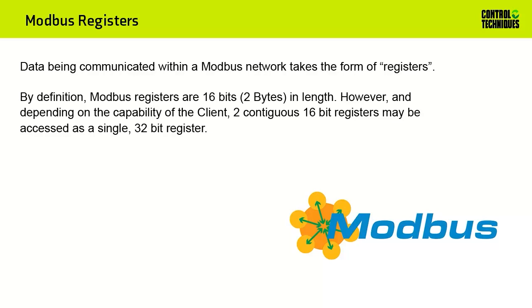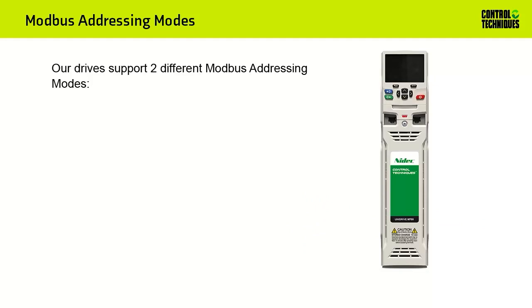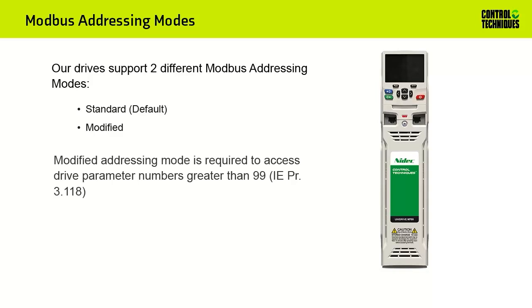By definition, Modbus registers are 16 bits in length. However, depending on the capability of the Modbus client, two contiguous 16-bit registers may be accessed as a single 32-bit register. Our drives support two different Modbus addressing modes: Standard mode, which is the default, and Modified mode. Modified addressing is required to access drive parameter numbers greater than parameter number 99.